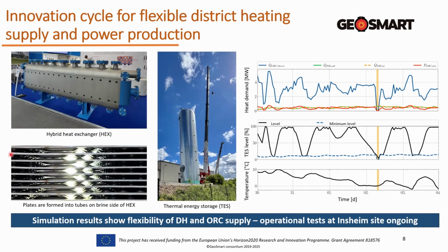In the lower picture, we see the plates that form a tube on one side. I lit it with a flashlight from the other side while taking this picture. This gap is about 8 millimeters, so these tubes are quite big compared to the 1-2 millimeter distance of plate exchangers. They're arranged so we can clean from top to bottom, which we still need to test.